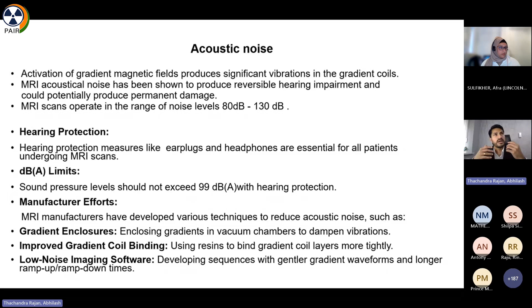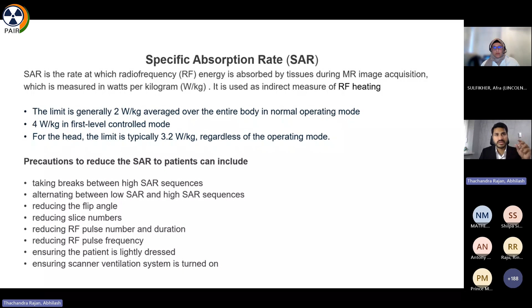We should know how to reduce the SAR while we are scanning a patient. We can take breaks between high SAR sequences, and we can also alternate low SAR and high SAR sequences, which will reduce the SAR. The main thing to remember is to dissipate the heat. If you put more and more blankets on the patient, heat dissipation will be less and the SAR levels will go high. We have to reduce the flip angle if the SAR is going high in a sequence, and also reduce the number of slices. In the case of RF pulses, we have to reduce the number of RF pulses. In TSE sequences, we can reduce the number of 180 degree RF pulses, and also the duration and the frequency of these pulses. We have to make sure that the patient is lightly dressed for the scan, and we have to increase the ventilation in the scanner room by turning on the fan inside the bore.